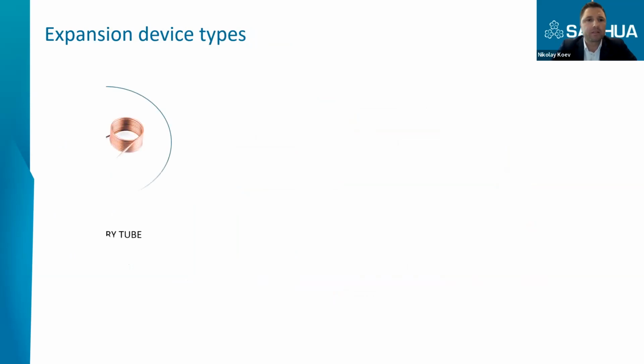So the simplest expansion device that I believe everybody knows is the capillary tube. It's a simple tube with a small diameter and certain length. Usually the capillary tubes are used in small capacity units with, let's say, constant heat load and stable working conditions. If there is a fluctuation in the working conditions, actually the system becomes inefficient. The capillary tube is not able to regulate the superheat. That's why the usage of the capillary tube is so limited.